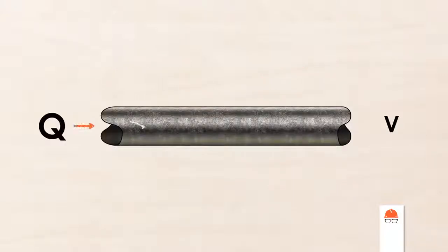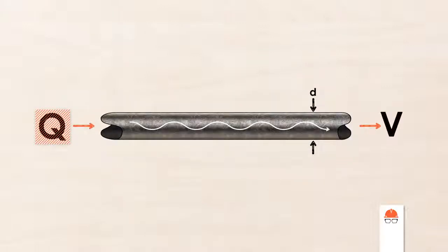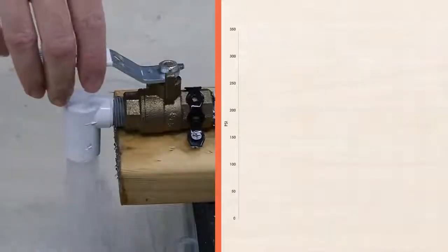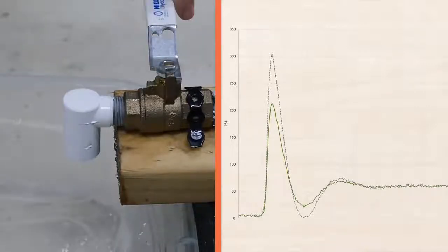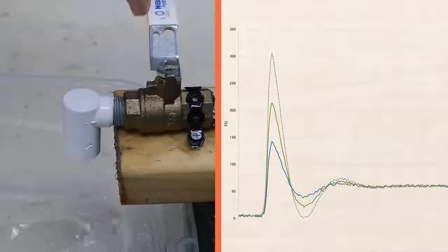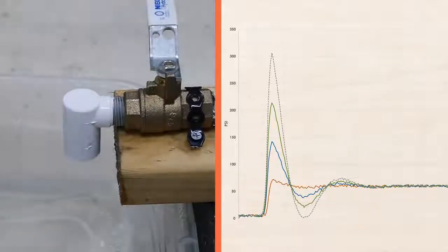Reducing this is one of the simplest ways to reduce the effect of water hammer. Velocity is a function of the flow rate and the size of the pipe. If you're designing a pipeline, the flow rate might be fixed so you can increase the size of your pipe to reduce the velocity. A smaller pipe may be less expensive, but the flow velocity will be higher, which may cause issues with water hammer. In this case, my pipe size is fixed, but I can reduce the flow rate to limit the velocity. Each time I reduce the velocity and close the valve, the resulting spike in pressure decreases.